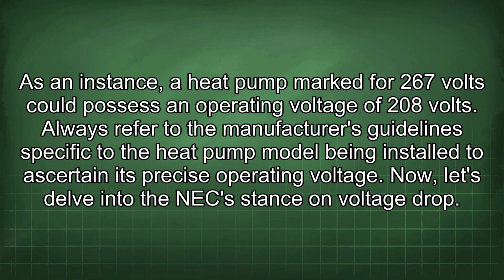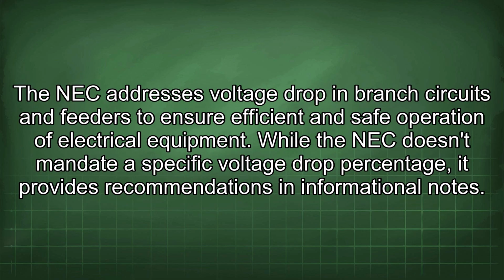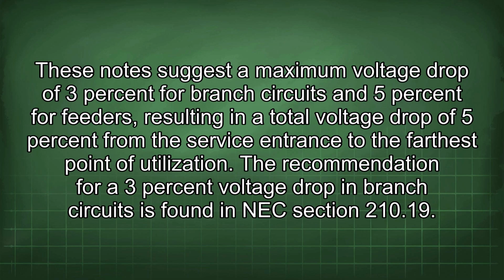Now let's delve into the NEC stance on voltage drop. The NEC addresses voltage drop in branch circuits and feeders to ensure efficient and safe operation of electrical equipment. While the NEC doesn't mandate a specific voltage drop percentage, it provides recommendations in informational notes. These notes suggest a maximum voltage drop of 3% for branch circuits and 5% for feeders, resulting in a total voltage drop of 5% from the service entrance to the farthest point of utilization.